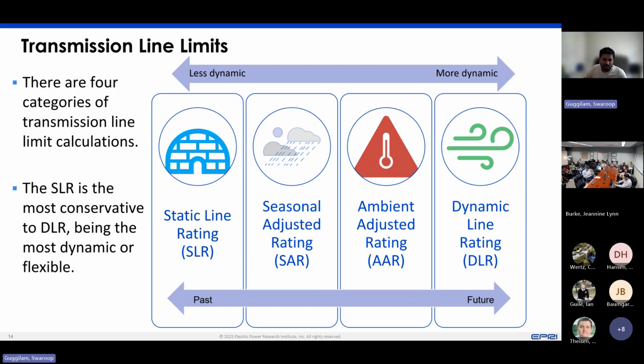And then people started thinking, why are we making assumptions? Why don't we use the actual live weather measurement and calculate the rating based on current situation and not historical or assumption based? And that's where ambient adjusted rating came in, where people now start putting sensors. They measure the actual temperature near the transmission line location and then calculate the rating based on that. So just your temperature is varying.